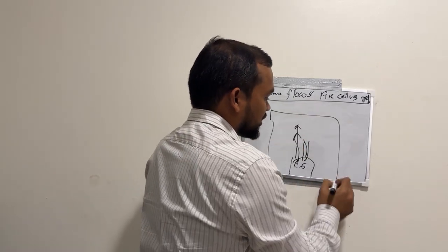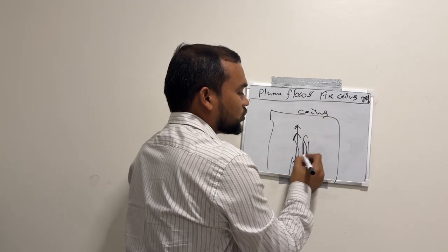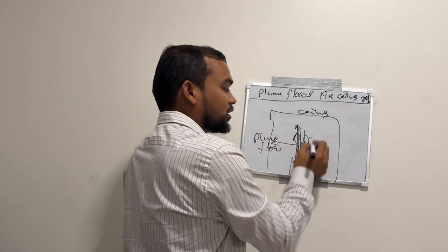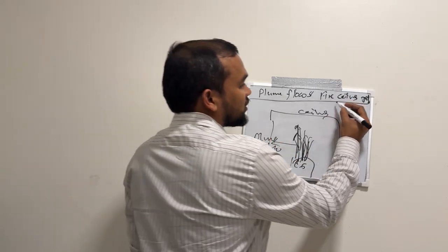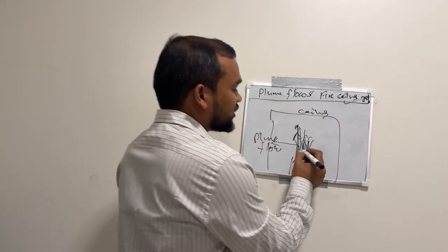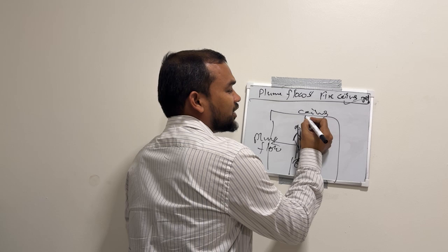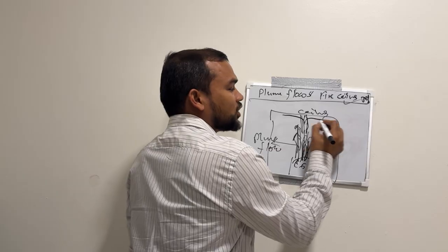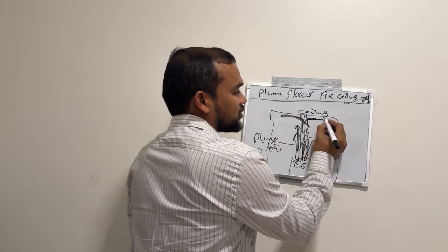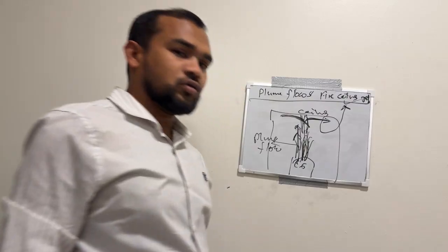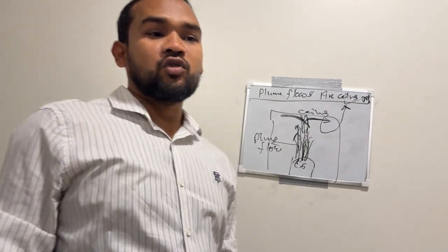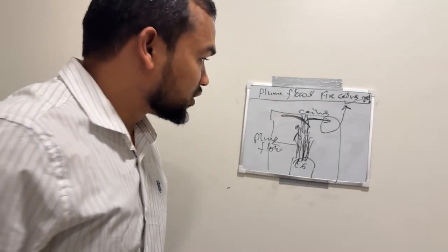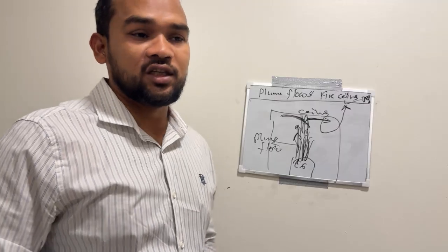And this is a structure, for example, this is the ceiling. When this goes up, this is called plume flow. Then hot air will go up. What is ceiling jet flow? In ceiling jet flow, the hot air and smoke rise and touch the ceiling. So it will contact the ceiling, then it will move horizontally. This is called ceiling jet flow. This is a very important characteristic in the selection of smoke detectors and heat detectors, and where we will install them.